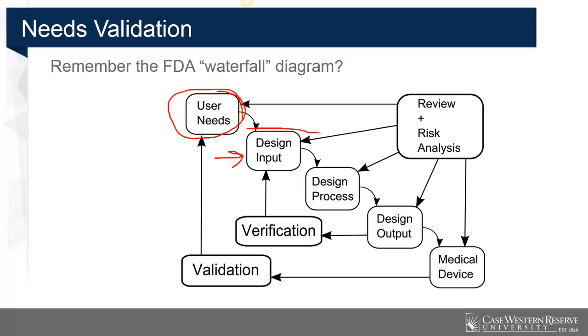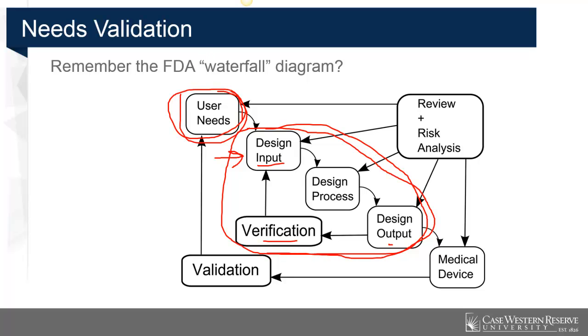And so typically what happens is engineers focus on what we call the verification process, and all of you are familiar with this. And really all it says is the verification is, does the output of the design match the input specifications? And this is a comfort zone for many biomedical engineers because the user need is often fairly vague. And of course, in this particular course, that's our emphasis. Big part of the course is focused on the user need.